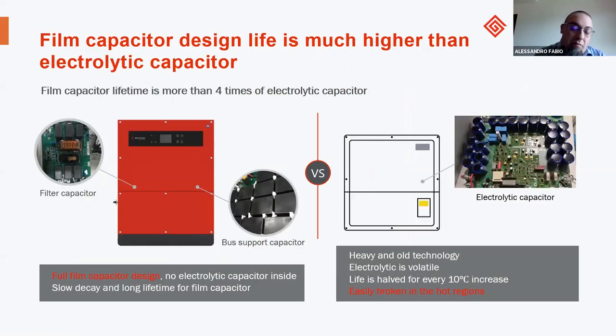One difference between the competitors and us is that we have used film capacitors for years, which are completely different from electrolytic ones, because they are also more efficient at high temperature. Also, the life cycle of the capacitor is really high. Electrolytic capacitors need a very stable temperature that is not so high, and need a cooling system inside the inverter that needs a lot of energy and reduces the efficiency of the inverter.